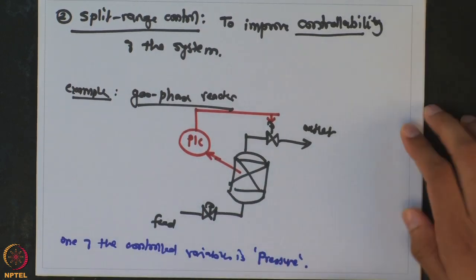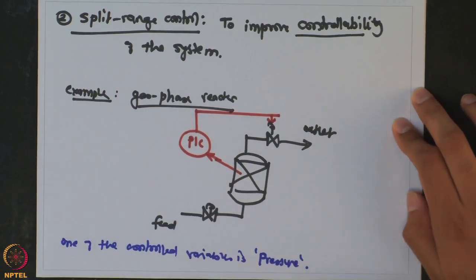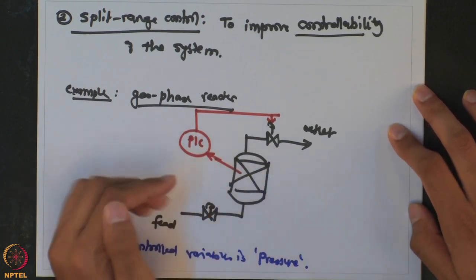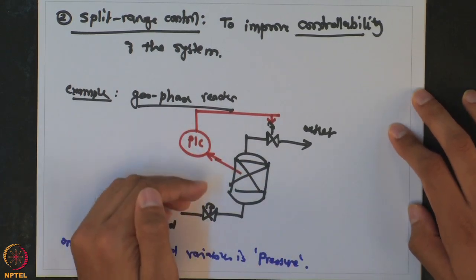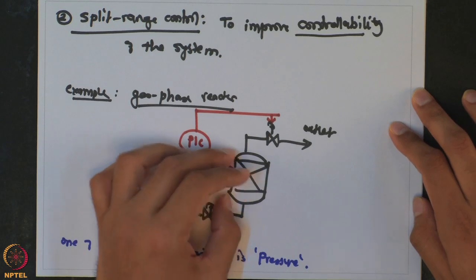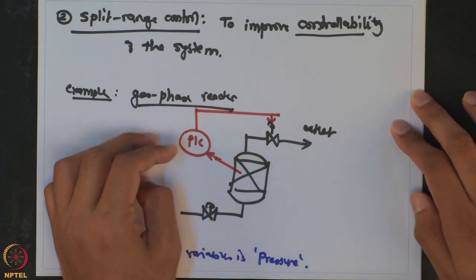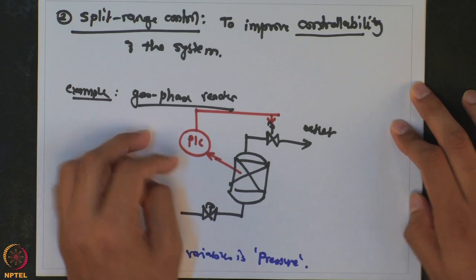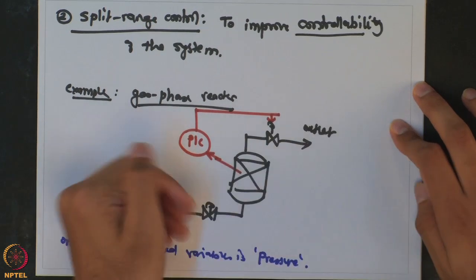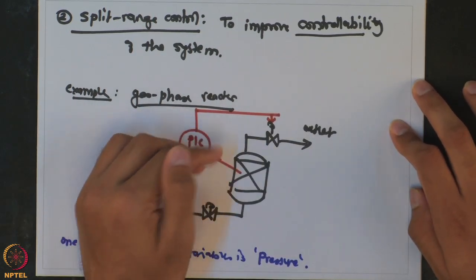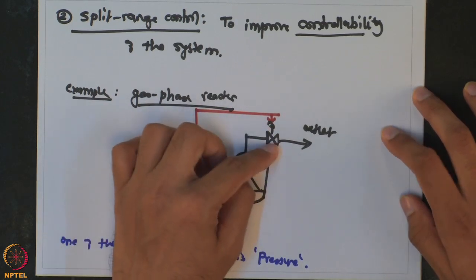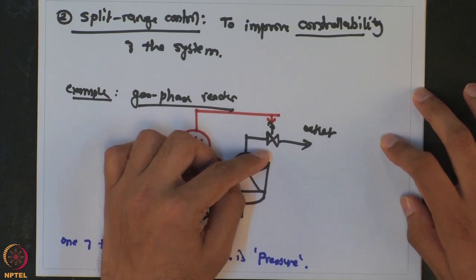Under normal circumstances, this is how the pressure controller works. If the pressure goes slightly above the set point, the outlet valve opens. If the pressure drops, you close the outlet valve to maintain vapor inventory inside the reactor. Now consider an abnormal situation where reactions are going into a runaway, generating a lot of vapor and causing pressure to keep increasing. As pressure increases, you open the outlet valve, but there is a limit — it can only open completely.